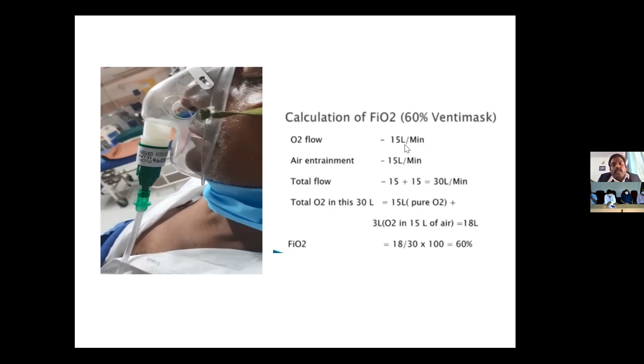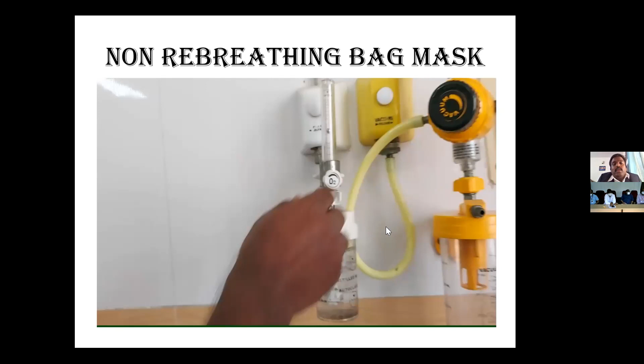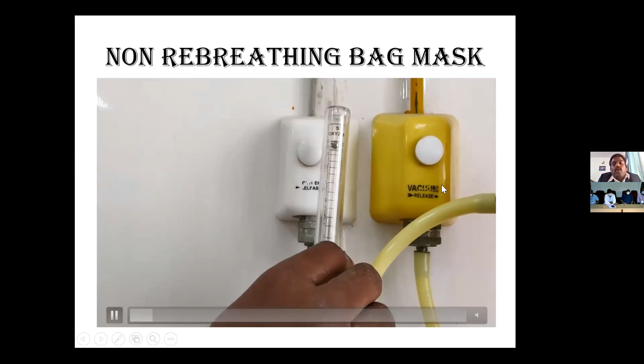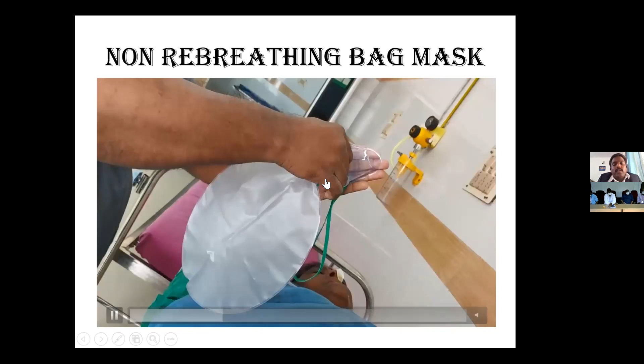So coming to the non-rebreathing mask, which we've routinely been using for severe COVID-19 and even moderate cases. In a non-rebreathing mask, the simple Hudson mask is designed in such a way that there is no rebreathing. So see how it works. Keep the flow more than 10 liters so that there is no rebreathing. Keep around 12 or 15 liters. And you have to make the bag get filled. At least 1/3 of the bag should be filled. The reservoir bag, about 300 to 500 ml, should get inflated before placing it on the patient. Now it is inflated.